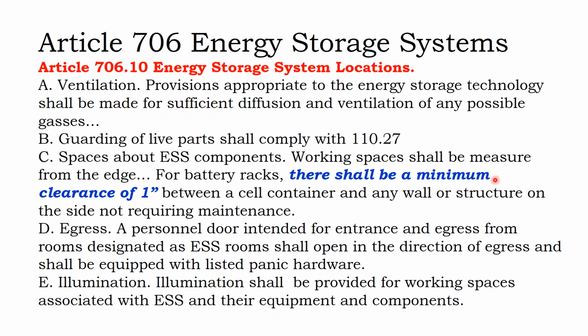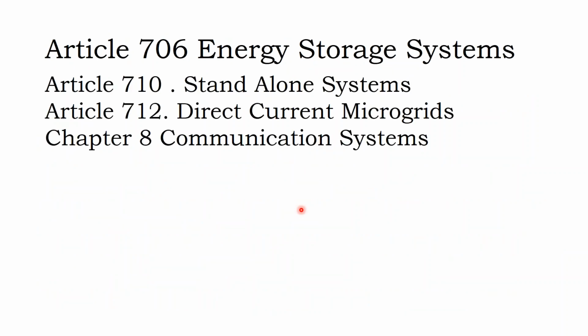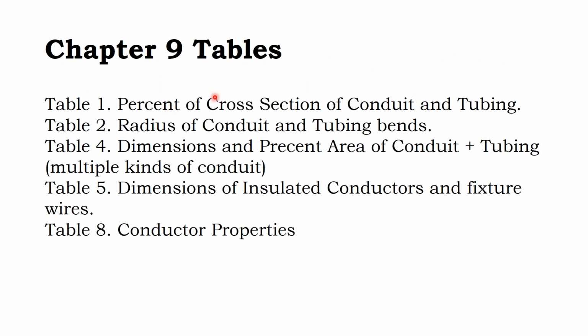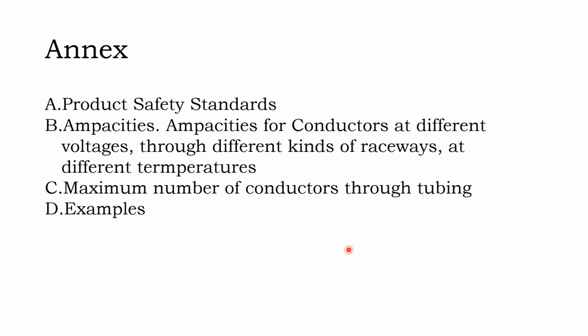You need 1 inch clearance between the batteries and the wall structures on sides that don't require maintenance. If they do require maintenance, you need your working space, which is 36 inches. Anywhere from 3 feet to 3.5 feet to 4 feet if you're back to back against another piece of electrical equipment. 706 is the energy storage system component, and then we get into microgrids, which is kind of a newer section. And then we get into the nice construction tables on the back for conduit bending and annexes. And that's the end of the program.